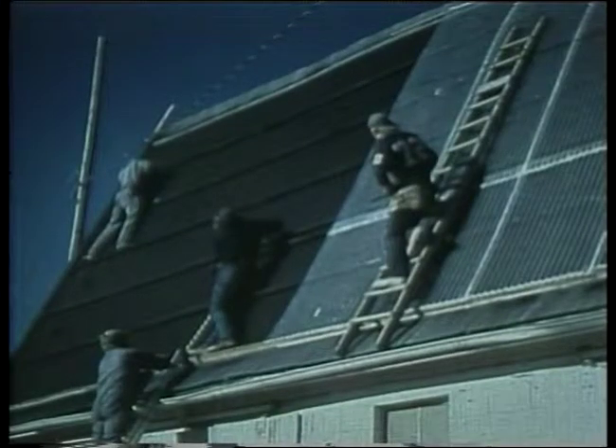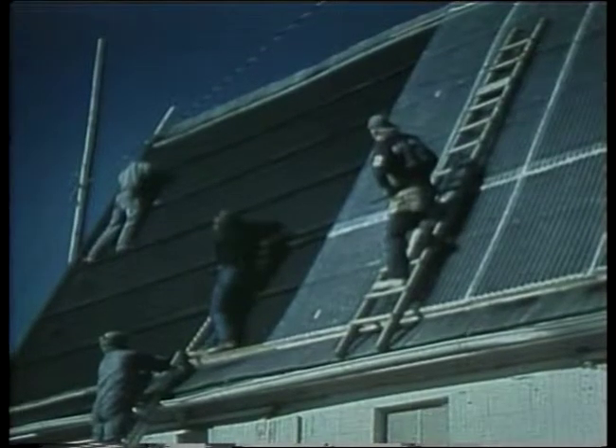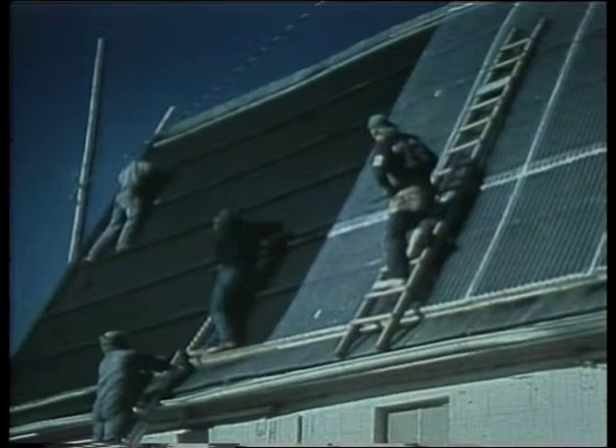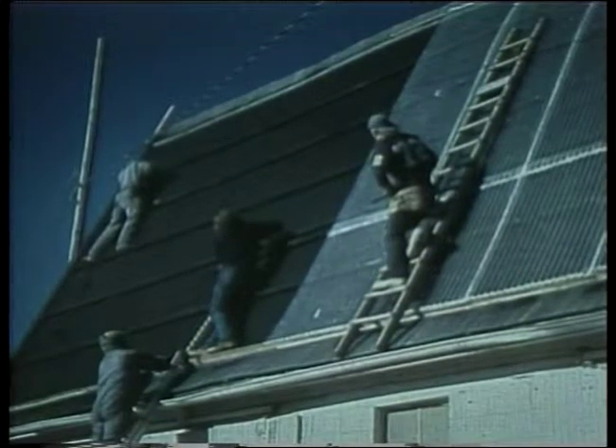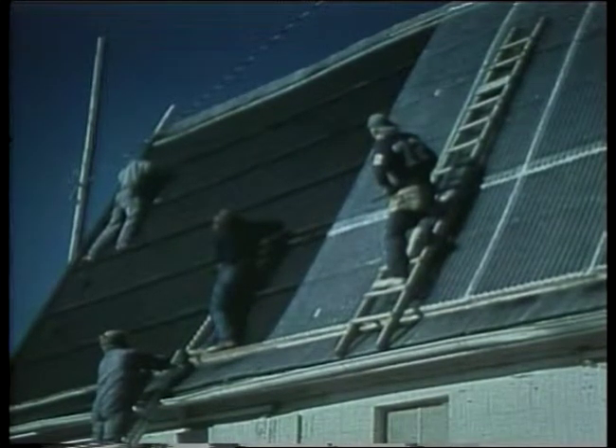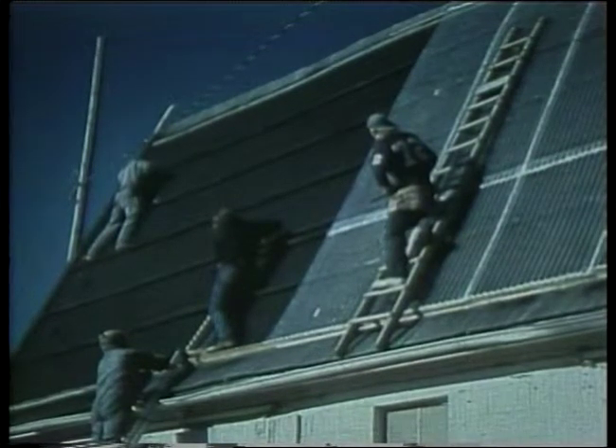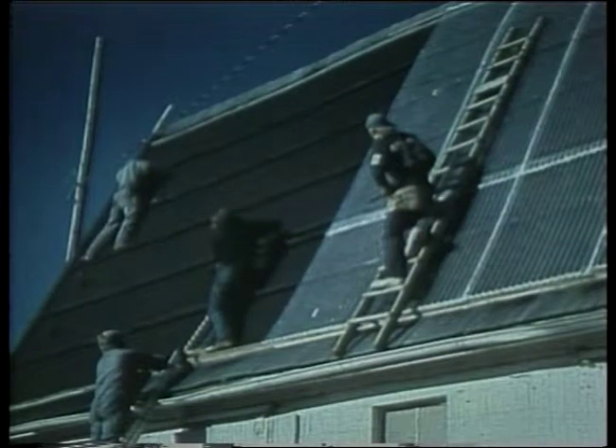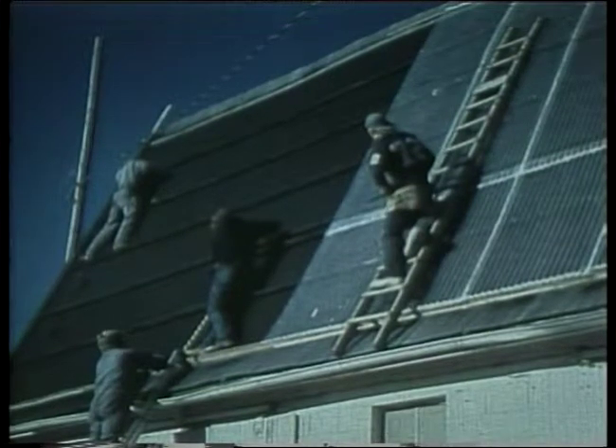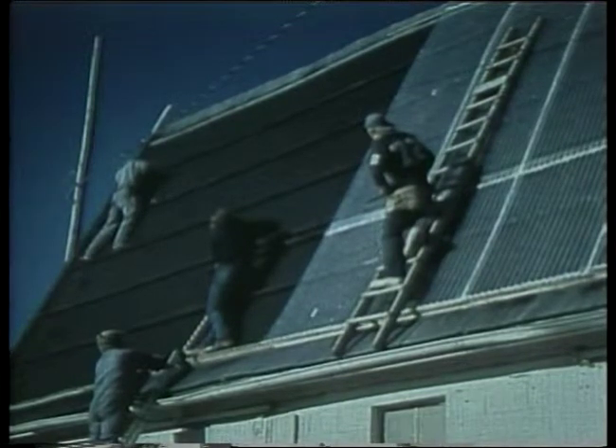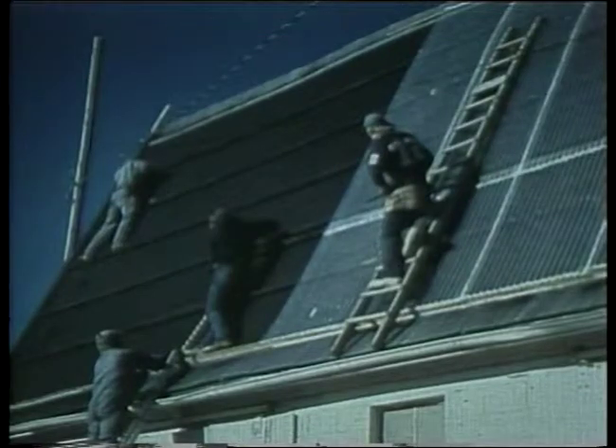This is an example of a site-built air type collector. You can see the pitch is 55 degrees approximately. It appears that the living space behind it can be utilized so that the insulation that must be there to protect the absorber is also insulating the house itself. And we see a lightweight cover going on there, which will be resistant to rocks and hail and not overweight the roof and require extra support.